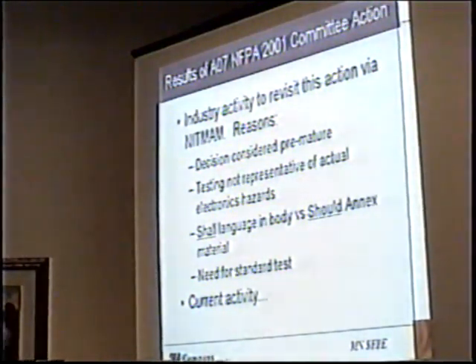And that they would argue this, you're going to make a motion on the floor at NFPA 2001, at the NFPA convention to debate this and try to get this turned back. And the decisions were considered premature, testing non-representative of actual electronic hazards. It's debatable in some of it, but one of the main things was that in a lot of the tests they used Nichrome wire. Nitro wire, basically it's toaster wire, and that wire would take you up to 1800 degrees. Typical copper wire will degrade or break at 900 degrees. It would fail. So there's a disconnect there.